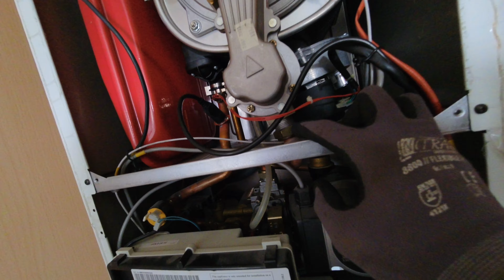Remember to put that back into the burner side, because if you don't, trust me, when the boiler fires up, you'll know. You've forgotten something and it will make you jump. Boom, literally, because that's what restricts the amount of gas going into the burner. If you don't put that in, you're going to be jumping. So don't forget that.